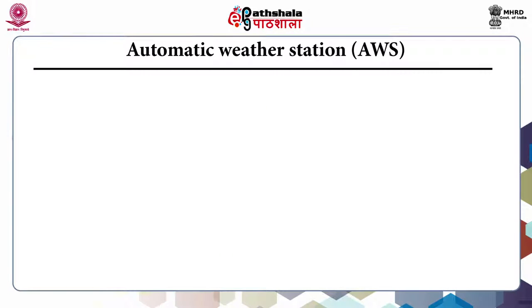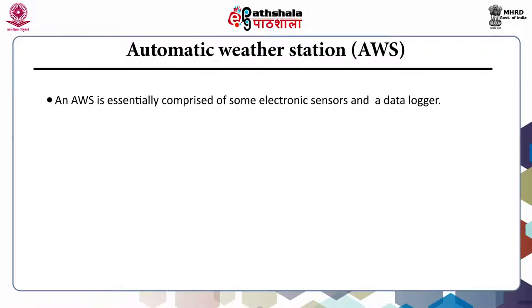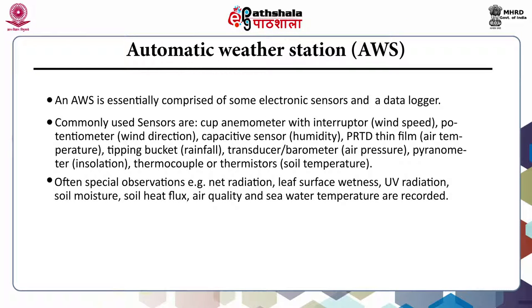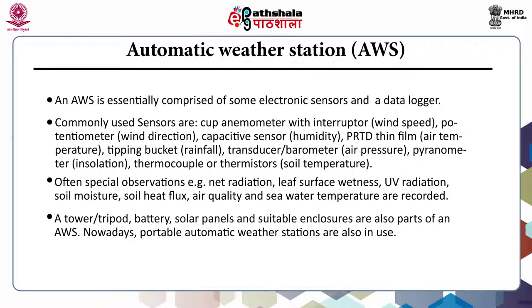Next is the automatic weather station. An automatic weather station is essentially comprised of electronic sensors and a data logger. Commonly used sensors are: cup anemometer for wind speed, potentiometer for wind direction, capacitive sensors for humidity, PRTD thin film for air temperature, tipping bucket for rainfall, transducer or barometer for air pressure, pyranometer for insolation, and thermocouple or thermistors for soil temperature. Special observations like net radiation, leaf surface wetness, ultraviolet radiation, soil moisture, soil heat flux, air quality parameters, and sea water temperature are also recorded. A tripod or tower is used to mount the sensors, and battery solar panels are an integral part of the AWS. Portable automatic weather stations are also in use.